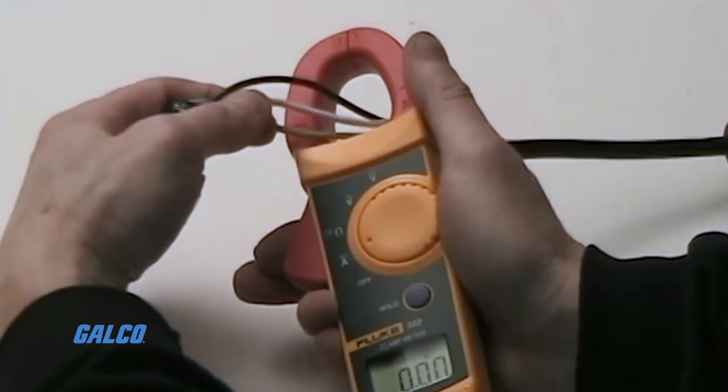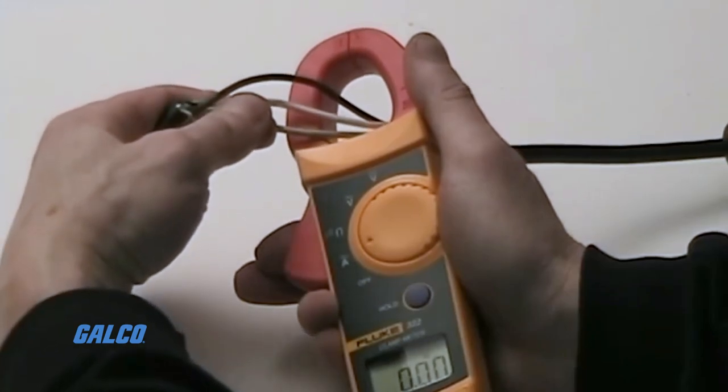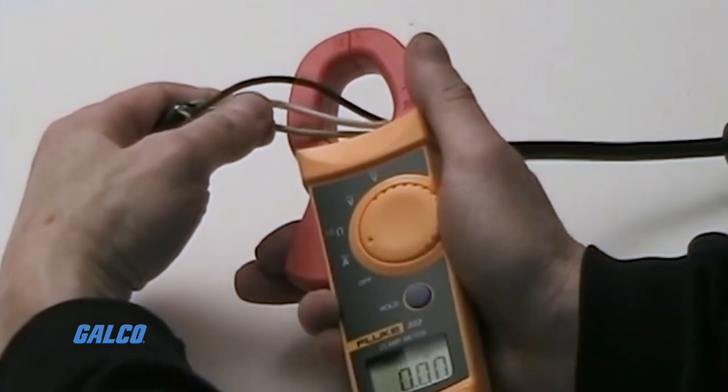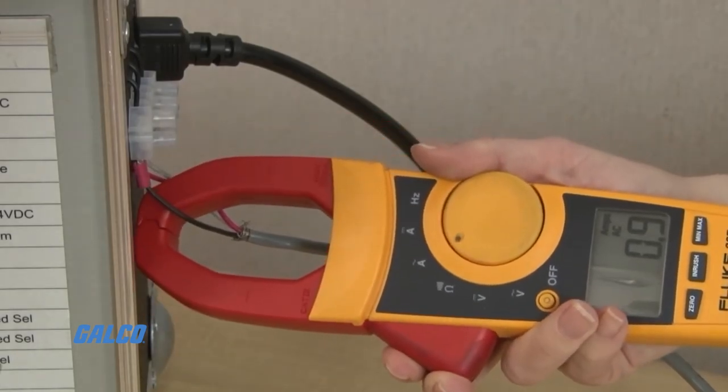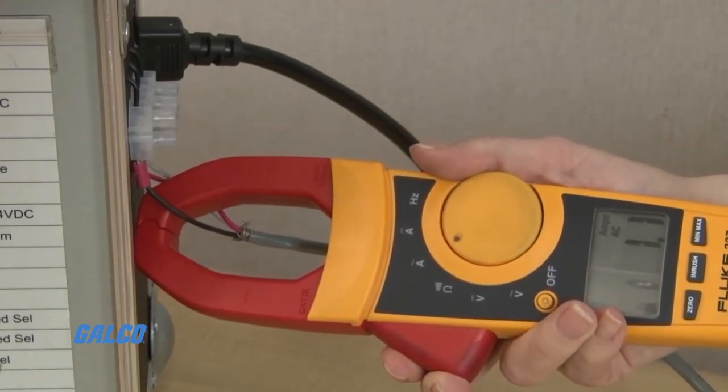So instead of getting a reading of 6 amps, you could get a reading of 0. Clamping around the hot wire or neutral wire in this case will give you the true current reading.